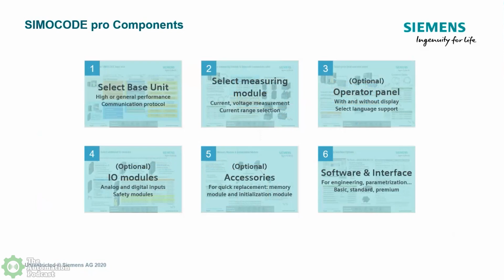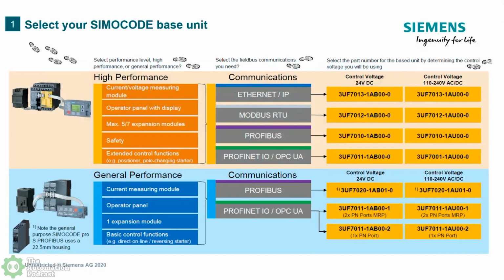There's many customers out there that still do 120 volt control. So we have a digital module that would add to that accessory and be able to use the 120 volt inputs for it. Quickly, here's kind of the part numbers. As we stated, the four main communication protocols that it does are Ethernet IP, Modbus RTU, Profibus, and then Profinet IO. And then you can see here the general purpose ones that I talked about with a little more cost effective. That's the Profibus and Profinet. But again, the web page and the OPC UA server are still available in the lower cost, the general performance one. It's not just in the high performance SIMOCODE.